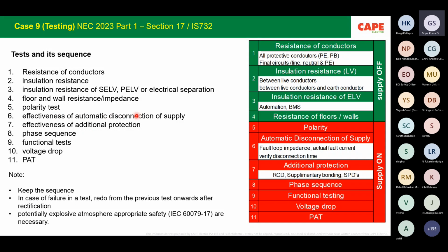For example, if you look at effectiveness of automatic disconnection, it is not simply taking a fault loop impedance meter, checking the fault loop impedance and finding out whether the MCB is tripping. That is 50% of the test. You should also test the effectiveness of automatic disconnection. So these are the 10 tests included, or 11 tests, in the National Electrical Code.